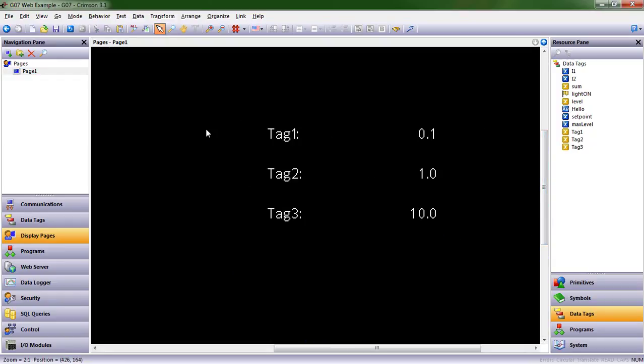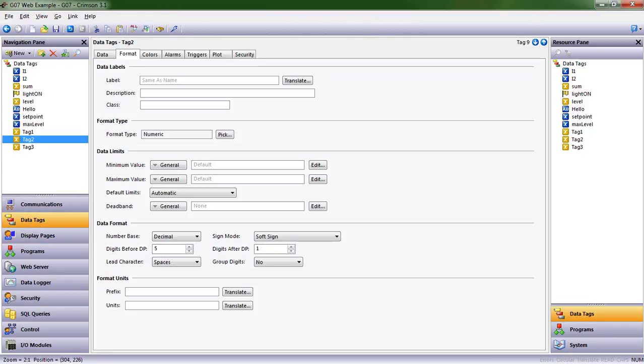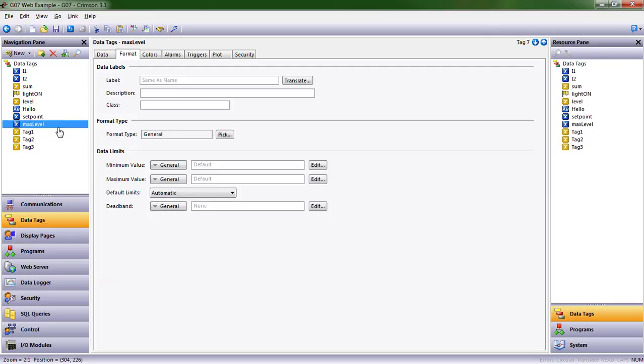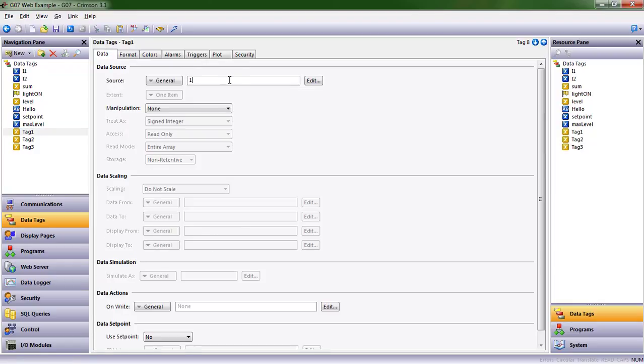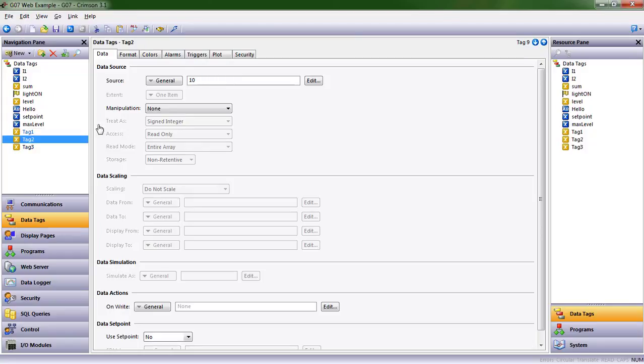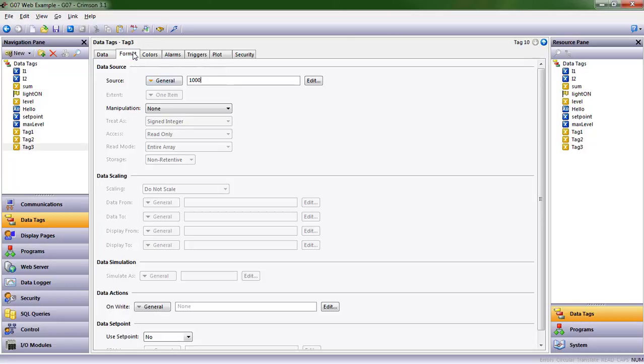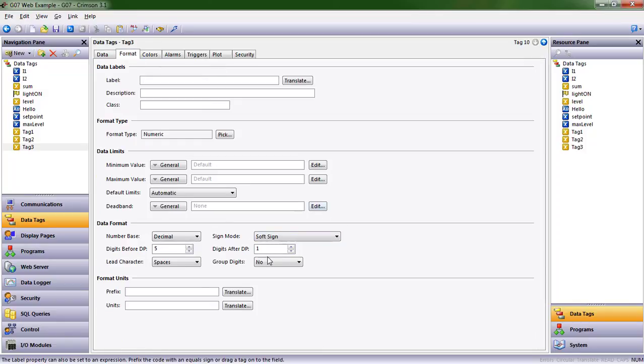So what happened though? I had 1, 10, 100 and now I've got 0.1, 1, 10. We have to start thinking about what we've told Crimson to display. Since we've asked it to display a value after the decimal point, we need to give it values that we expect to see on the screen, taking into account that extra position. So 1 becomes 10, 10 becomes 100, and 100 becomes 1000. In reality, this is still 100.